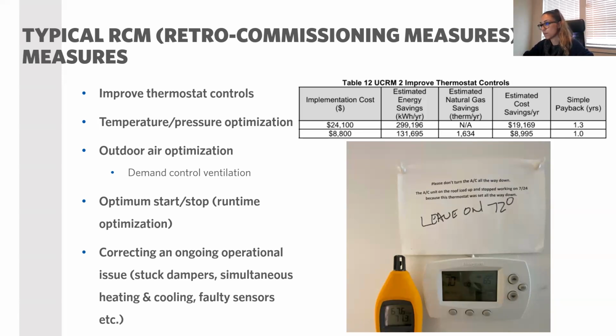So this is an interesting picture that I took on site, which I think is really funny. I mean, improving thermostat controls is the number 1 ECM we recommend all the time, and it doesn't matter what type of building, this is always an issue because you're intermingling with people's comfort levels. Apparently this building had a problem before. They mentioned, please don't turn the AC all the way down. Once they did this, the roof unit iced up and stopped working, and the thermostat was set all the way down. So that's why they recommended leaving it at 72.